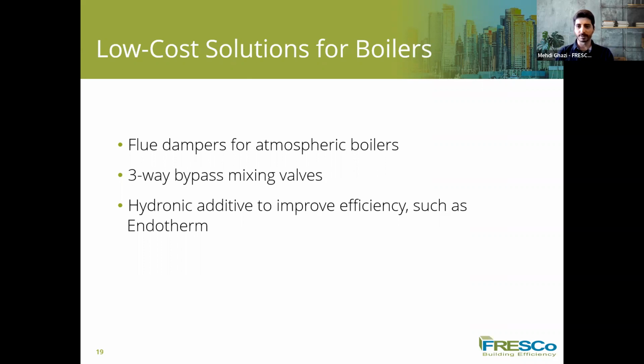Most older boilers are massively oversized, actually. They fire at only 25% to 50% of capacity, even on the coldest day of the year, and most of the time they only need to fire for a short time, and then they remain off for a long time. So it can quite often happen that when they are off, we waste energy through the flue vent. And dampers could help in preventing this. Another solution is a three-way bypass mixing valve.